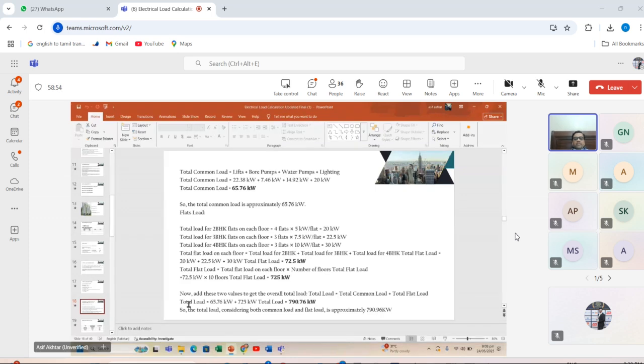Now add these two values to get the overall total floor load. The total load is equal to the total common load plus the flat load. We also add the total common load in this calculation for main transformer sizing. So the total load is 65.76 kilowatts common load plus 725 kilowatts. If we add these two, we get 790.76 kilowatts. So the total load considering both common load and flat load is approximately 790.6 kilowatts.